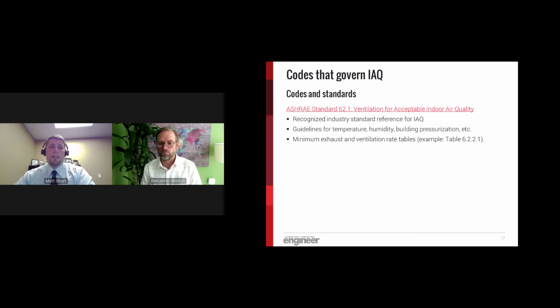So now that we understand exactly what indoor air quality is, I'd like to discuss in greater detail the codes and standards that apply to these design considerations that Benny introduced earlier. Starting out with ASHRAE Standard 62.1, this is a standard that's recognized almost universally as the industry standard for indoor air quality. Within this standard, designers will have access to guidelines for temperature, humidity control, building pressurization, and many other design criteria that's impactful for indoor air quality. One of the most commonly applied and useful tools within this standard is the minimum exhaust rate and ventilation table, which is Table 6.2.2.1. This is a table that provides guidelines for various spaces that'll help the designer determine a minimum amount of fresh air to provide to a space and the required exhaust air to remove from a space.